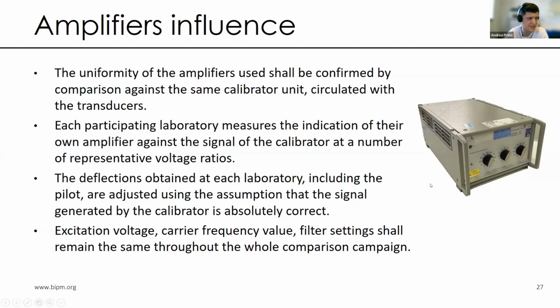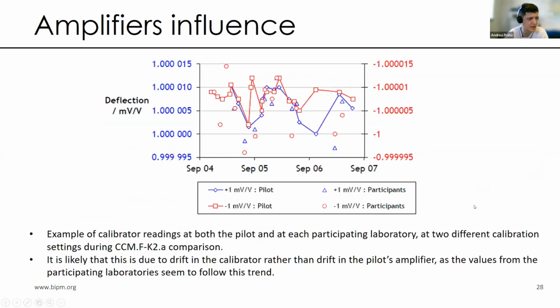Another key aspect is that the excitation voltage, the carrier frequency, and also the filter settings shall be the same throughout the whole comparison in order to minimize the influence of these amplifiers. We can see an example of the behavior of the amplifiers, both at participants and at pilot laboratories, and we can see the different voltage steps here, plus 1 millivolt per volt and minus 1 millivolt per volt, and we can see the time series for these two voltage ratios at the pilots and participants. We can see a similar behavior. So despite different amplifiers being used, we can see a similar behavior.